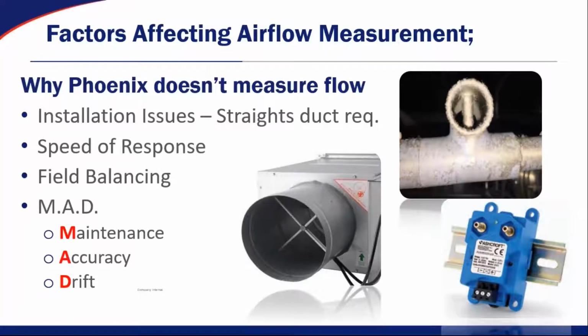So different factors that affect airflow measurement and why Phoenix doesn't measure flow. So we talked about with a Phoenix valve, you don't need straight duct runs. Well, in order to get an accurate measurement and an accurate flow control inside of a flow measurement device, you have to have straight duct runs. You're always going to have a reduced speed of response because you have measurement delays. There's always going to be a level of field balancing involved in this, which is going to take considerably more time to start up, which also means that there's going to be maintenance, there's going to be accuracy shift over time, and there's going to be drift over time. So let's take those three pieces one at a time.